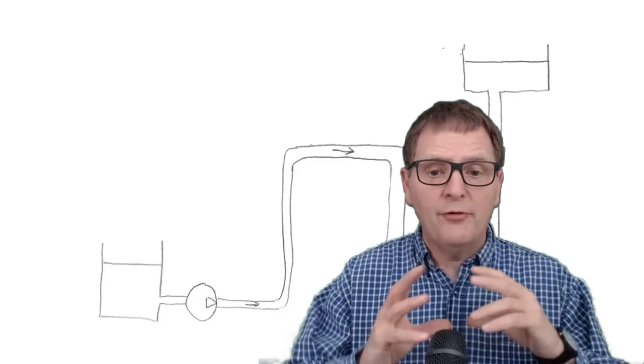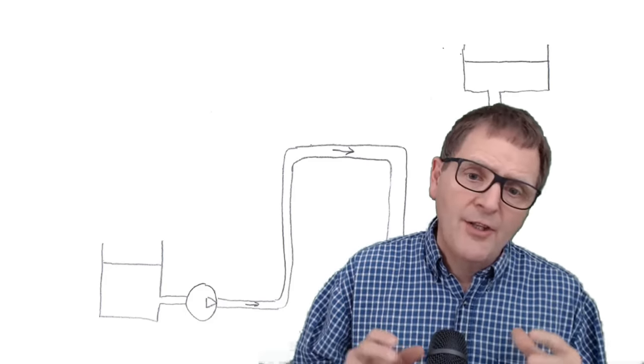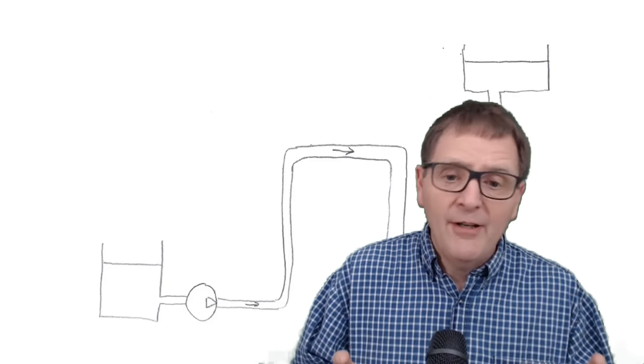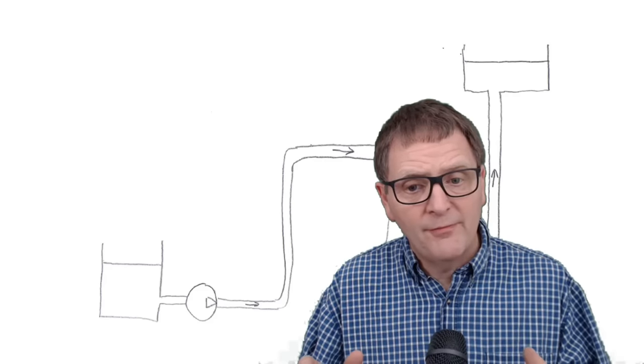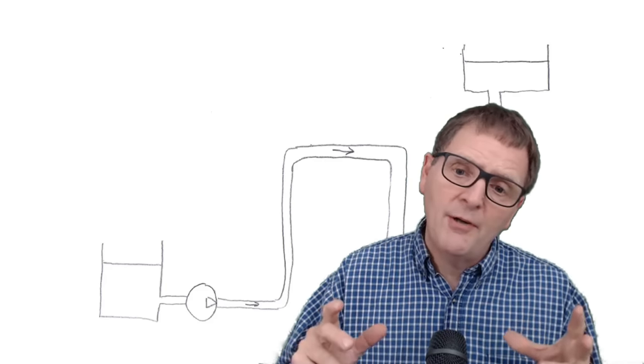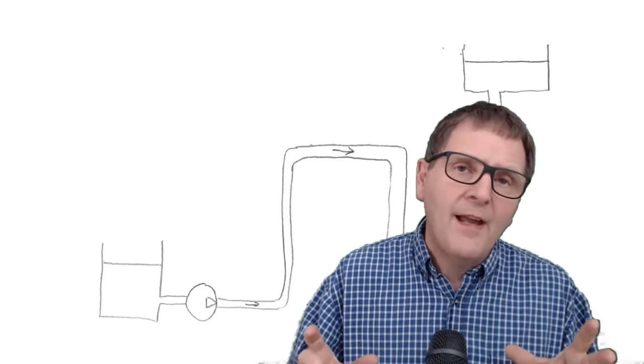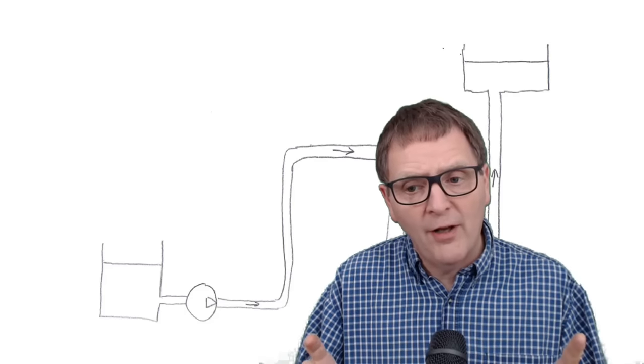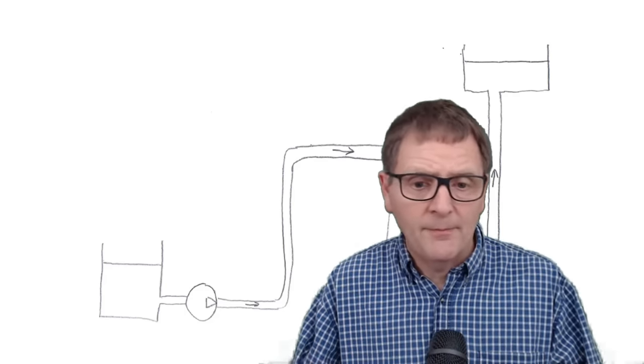These pockets cause a restriction. This reduces the flow area and increases the pressure loss and increases noise. In this lesson I will show you how to identify when there is a potential problem with waterfall flow and how to calculate the pressure drop.